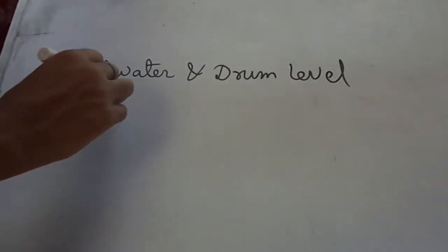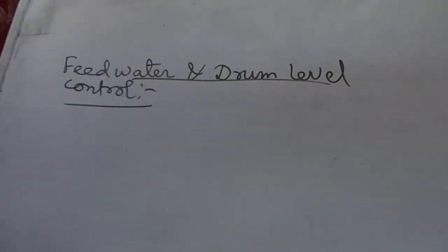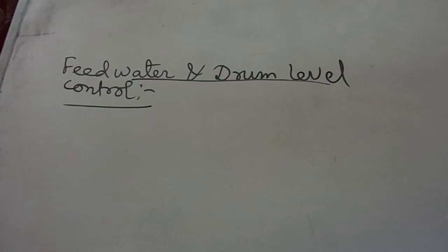Today I am discussing feed water and drum level control. Feed water and steam flow are controlled to meet load demand by the turbine and, at the same time, maintain the level of water in the steam drum within relatively narrow limits.